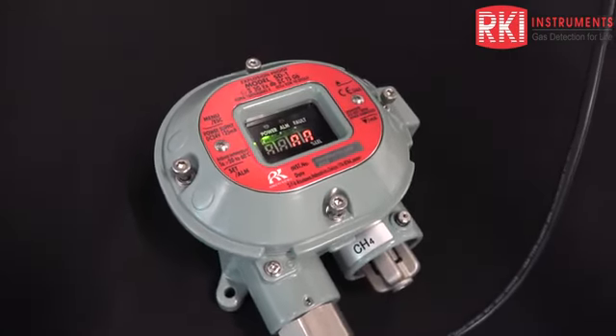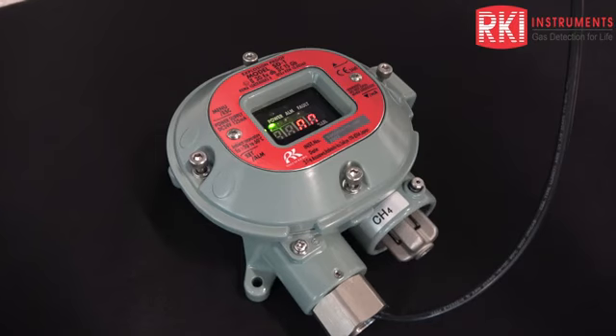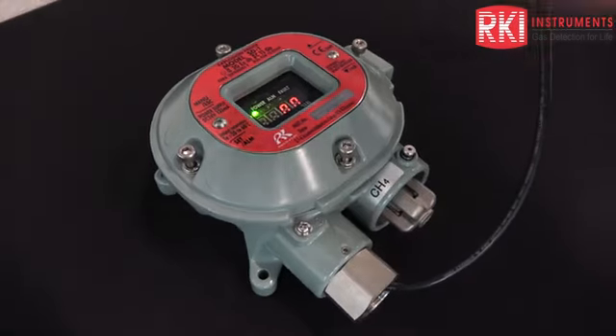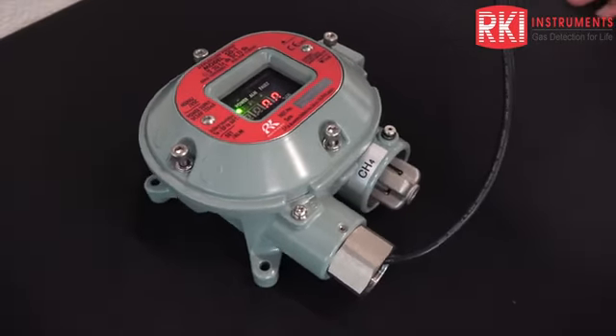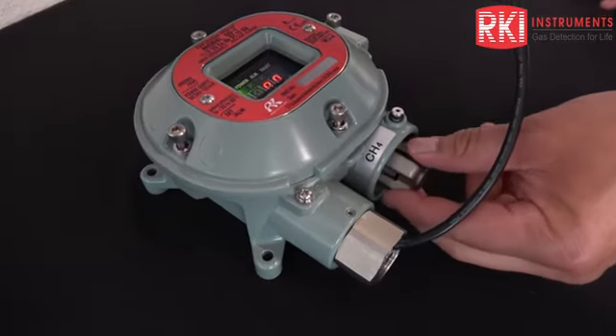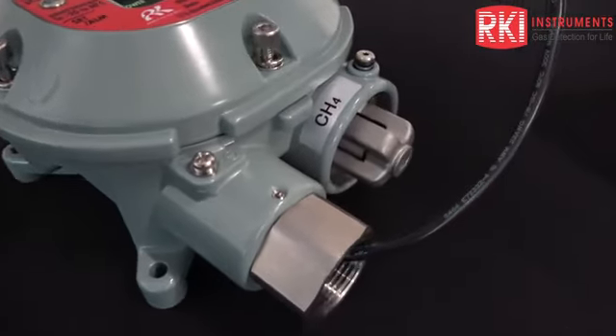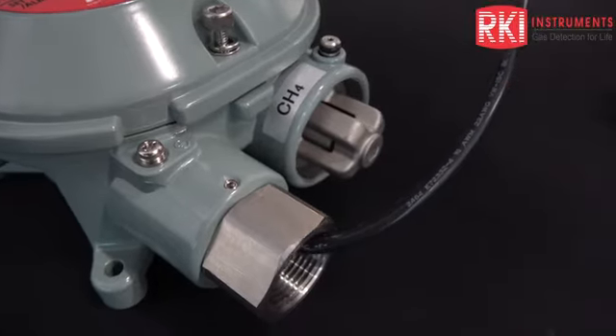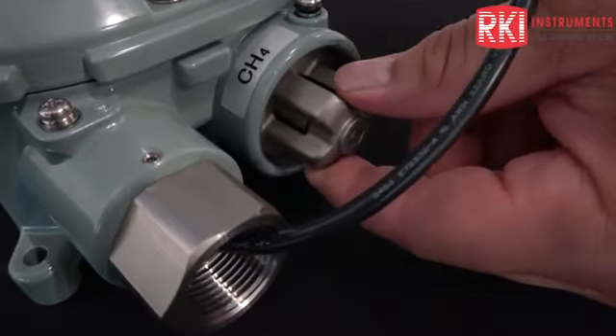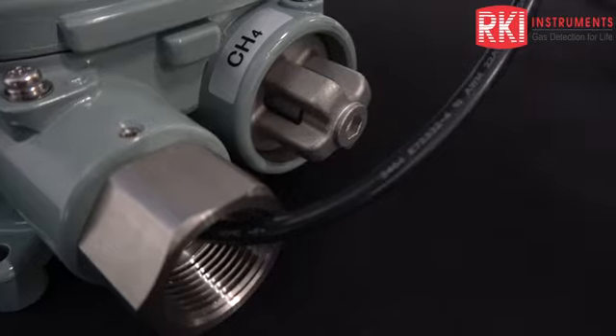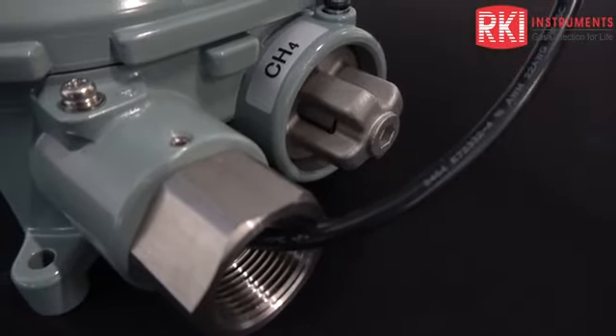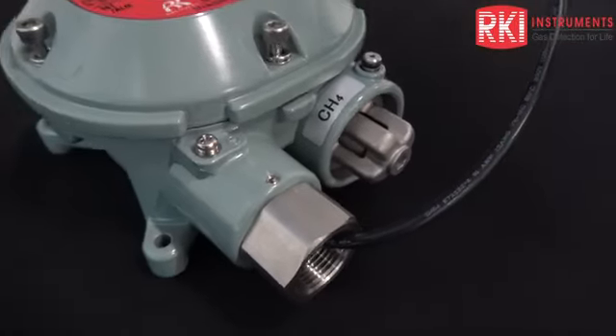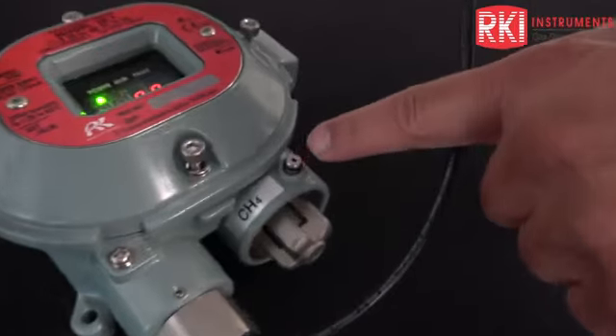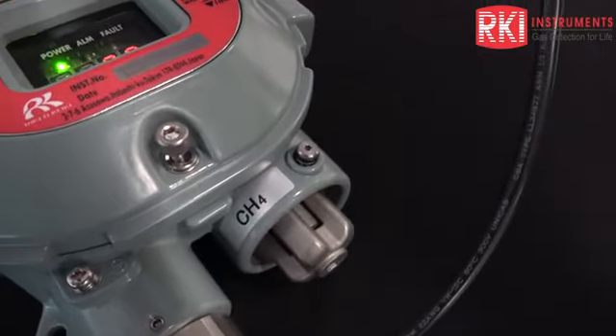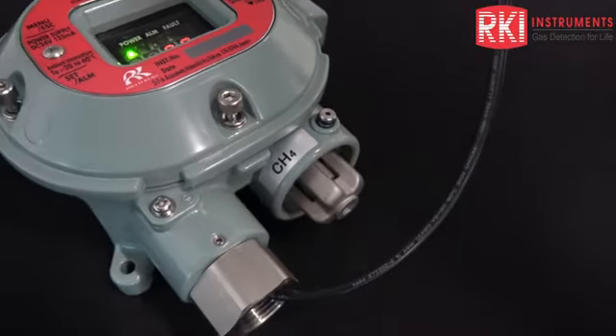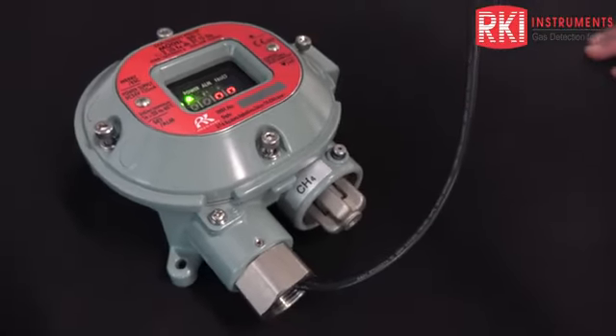So if you're going to be detecting benzene in a ppm range, then your detector head would have a yellow label. Otherwise the sensor assembly would look pretty much the same. The sensor itself is a plug-in type of sensor, and then the sensor guard here just threads into the assembly and cinches that sensor tight, so it's nice and snug. Then you have a little set screw here that you can tighten up the guard so that no one can take the guard off from around the flame arrestor.